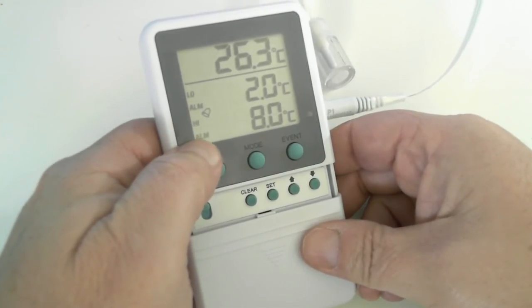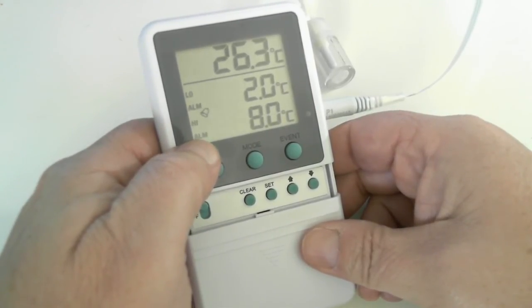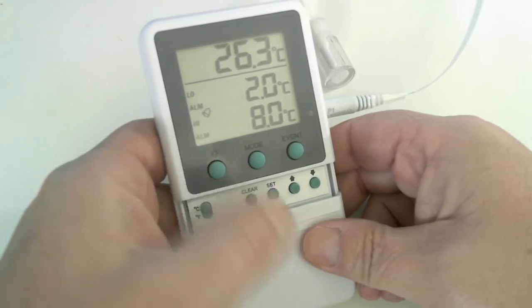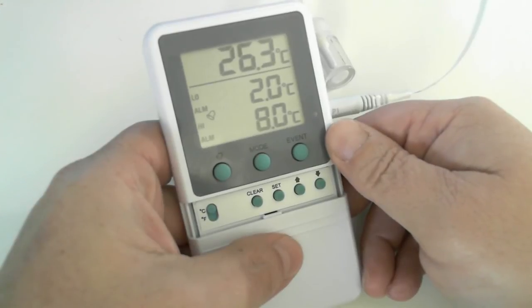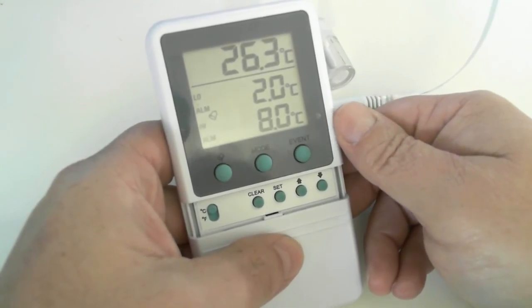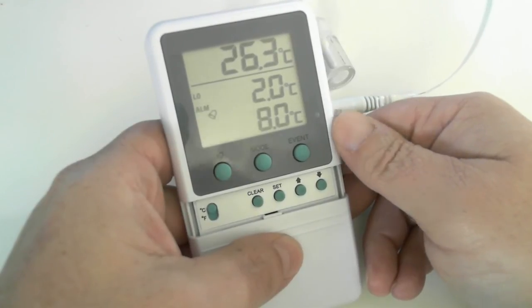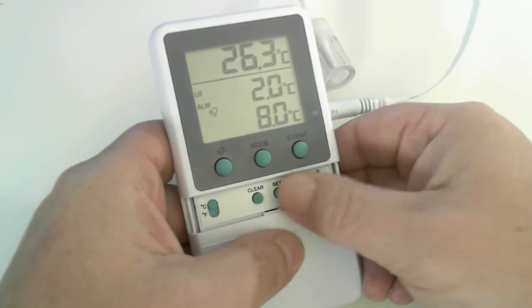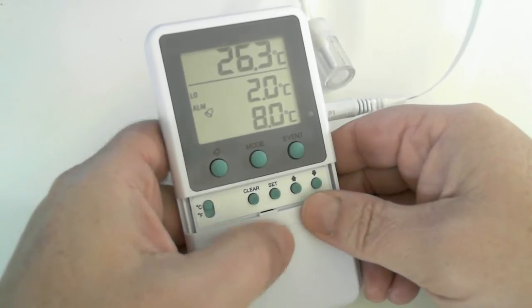All right. The LCD screen is showing you a flashing high alarm, meaning that you had an excursion with your high alarm set point. You have a red LED blinking, and you also have the audible alarm. It beeps about 10 times, goes silent for a bit, beeps 10 more times, and will continue until you hit any button, which will silence it.